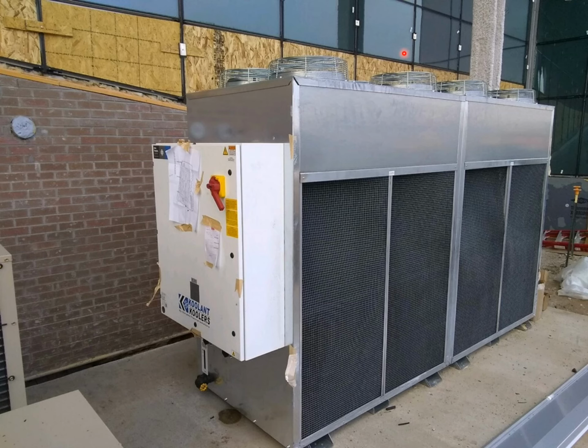And these are pulling air through here to do our thing with the refrigerant. That's exactly what's happening here. So this isn't a gigantic chiller by any means, but it is cooling what they need to cool, whether it's computer rooms or just cooling for folks, or machinery that's going on inside there, and they want cold water. So cold water goes in, goes through a VAV box, air is moving through it, and cools the air. Warm water comes back, gets chilled again from the refrigerant unit, goes back into the building. It's a never-ending loop. So yeah, that's a chiller.